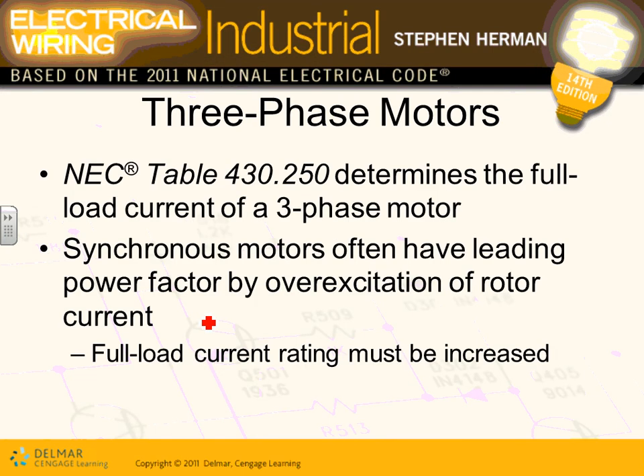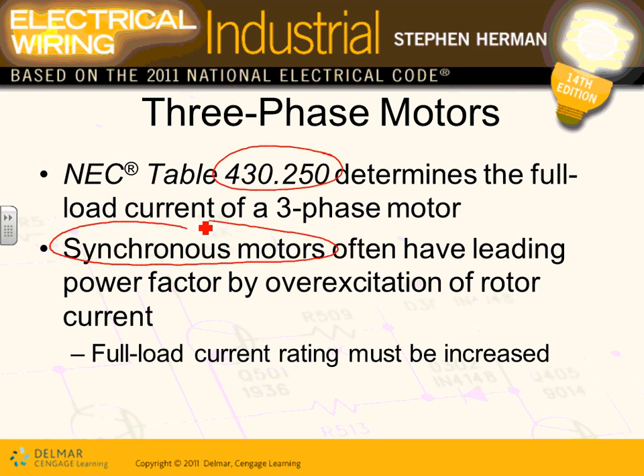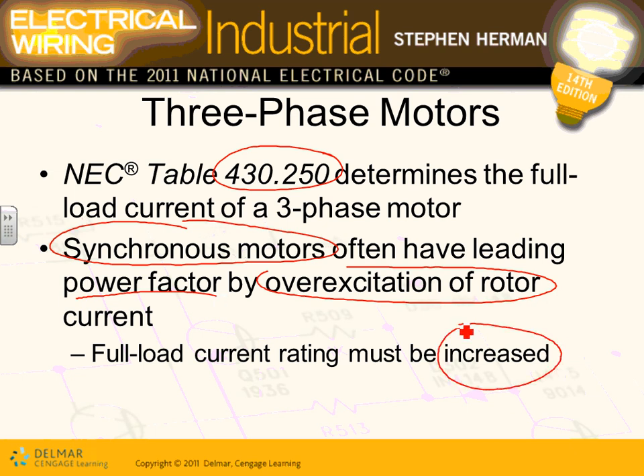For three-phase motors, full load current is determined from the NEC table. For synchronous motors, if you over-excite them the power factor changes, so you must increase the amps using the multipliers at the bottom of table 430.250, based on the power factor.